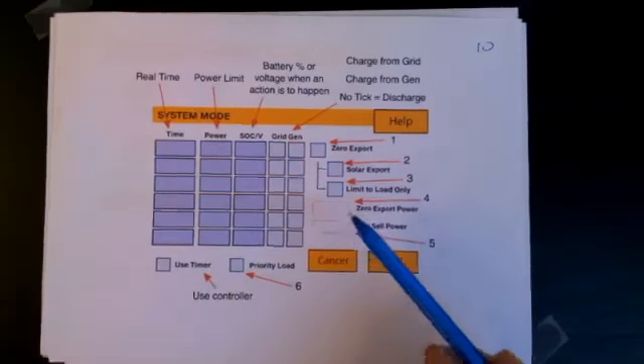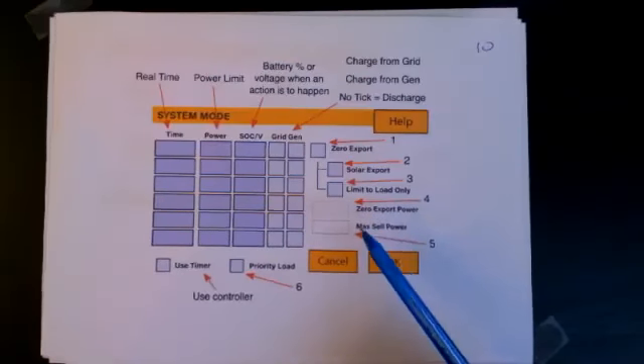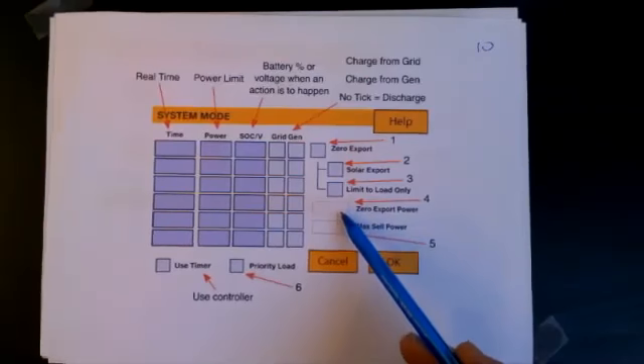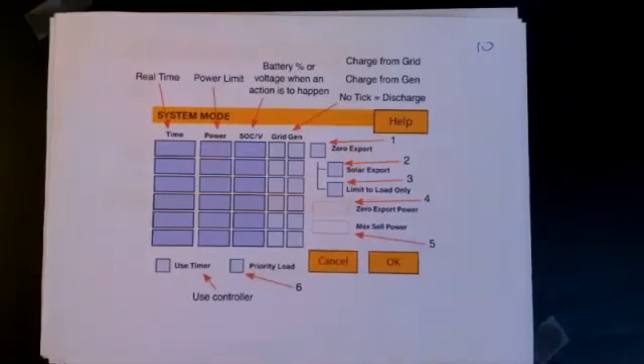You choose, and I can explain a little bit more about that in a second. Zero export power. This is actually for prepaid meters, and it's specifically designed for South Africa. So often on a prepaid meter, an electric meter, you've got the power coming into the meter. The problem with the prepaid meter is if you try to export power back through it, it will lock out, it will shut down, it will trip. And that's what it's supposed to do, because you can't export off a prepaid meter, because maybe people try to make them go backwards, I don't know, but you can't export.